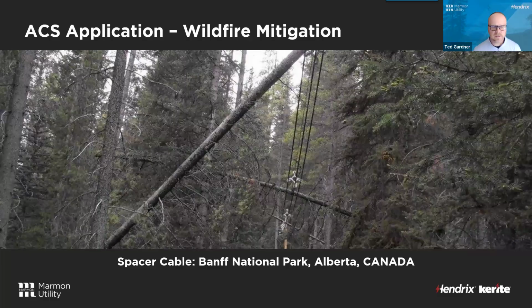Wildfire mitigation is obviously a pretty hot topic, no pun intended, right now. I'm not sure up in Canada if that was one of the concerns when they put this in, but it's a good picture to show what they deal with. This is an older circuit that's been up for quite some time. The reason they use spacer cable here is they can only get to this spot in Banff National Park a few months out of the year. The rest of the time it's hard to get to, and there's enough snow in there. So they do come out here twice a year and do a walk-down inspection. And a lot of times their vegetation management group has to cut some of these trees off.